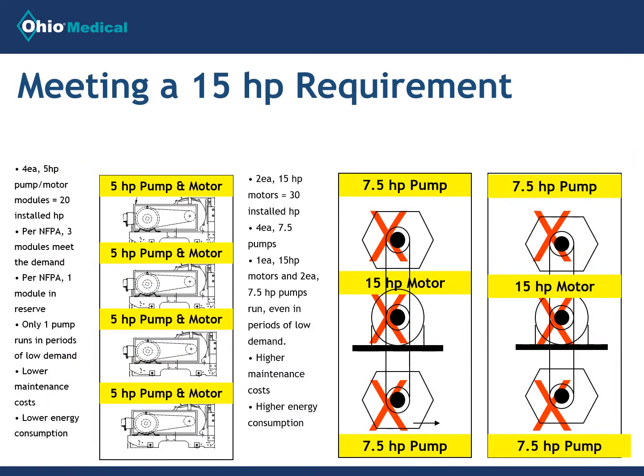The Ohio Medical design can also be more energy efficient, as a 15 horsepower system specification can be met with three 5-horsepower scrolls plus a backup unit for a total of 20 installed horsepower. Compare this to a system with shared motors and four 7.5 horsepower scrolls with a total of 30 installed horsepower. Also, the Ohio system provides variable flow by staging compressors that are activated as demand grows.